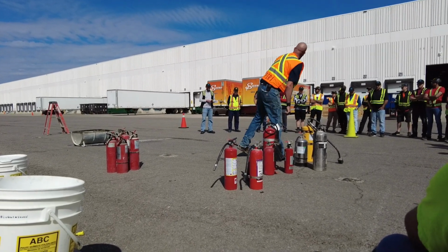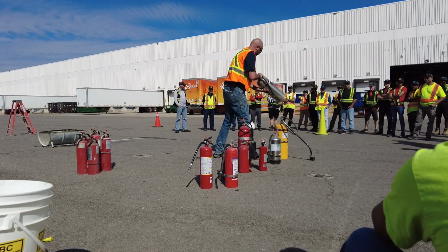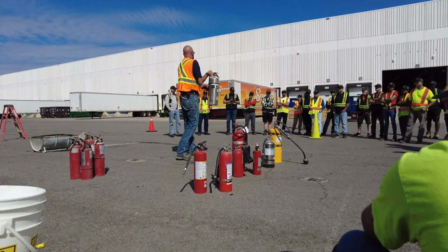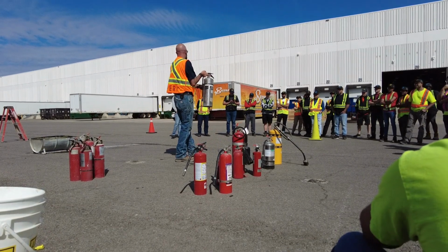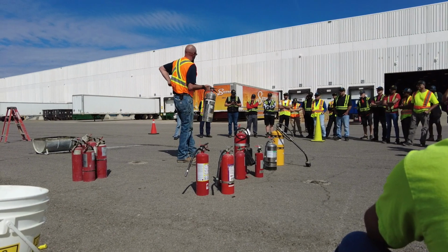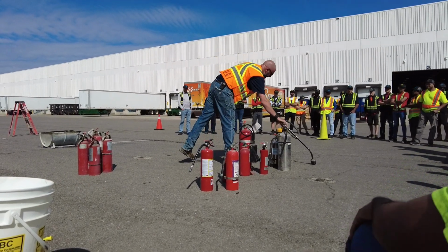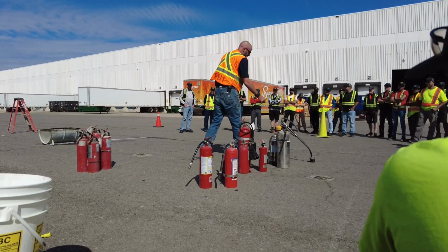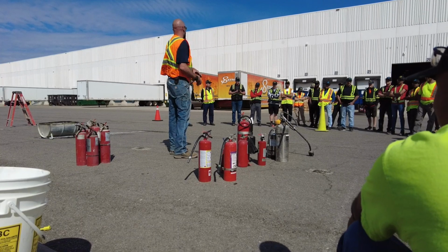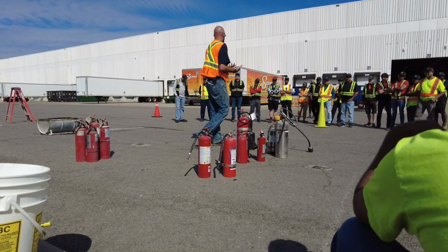Okay. What's that? Yeah, what we do is fill it up to about here. There's an overflow tube. Fill it up with 2.5 gallons of water, and then put about 100 psi of either dry compressed air or nitrogen in, and that's what we use to push the water back out. And basically the powder ones are the same thing. We fill them with the powder, and use nitrogen to push the powder out when they're being used.